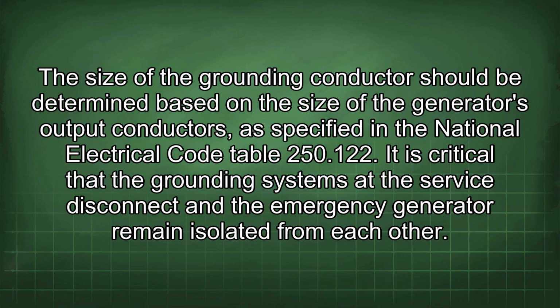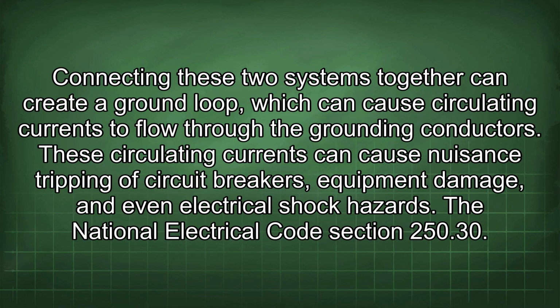250.122. It is critical that the grounding systems at the service disconnect and the emergency generator remain isolated from each other. Connecting these two systems together can create a ground loop, which can cause circulating currents to flow through the grounding conductors. These circulating currents can cause nuisance tripping of circuit breakers, equipment damage, and even electrical shock hazards.